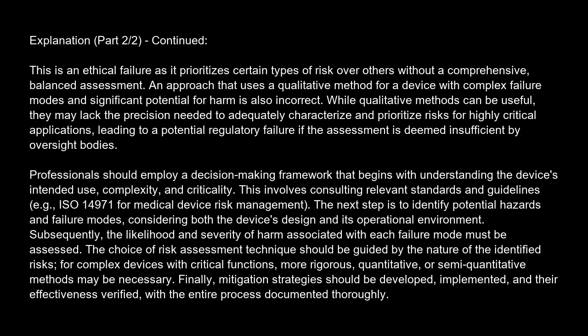Professionals should employ a decision-making framework that begins with understanding the device's intended use, complexity, and criticality. This involves consulting relevant standards and guidelines, e.g. ISO 14971 for medical device risk management.